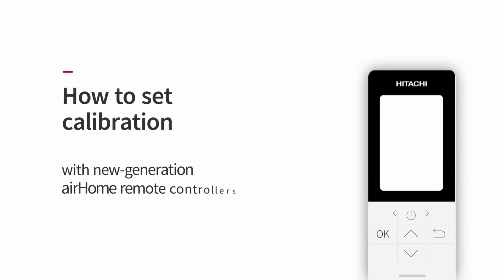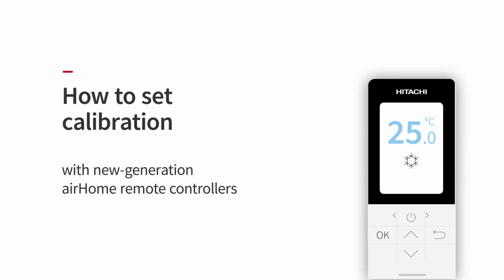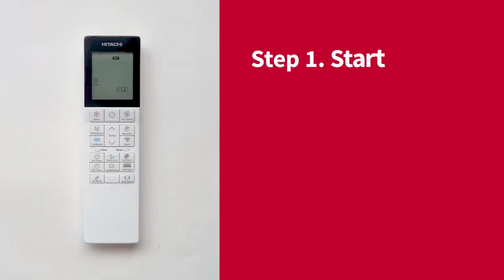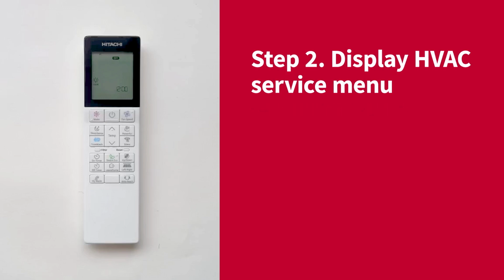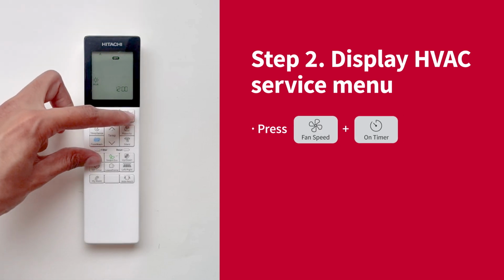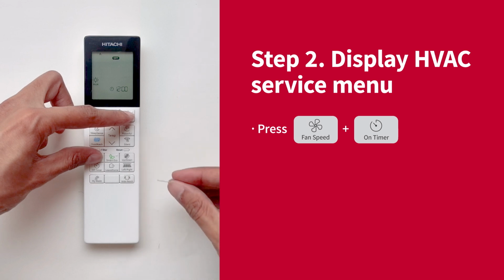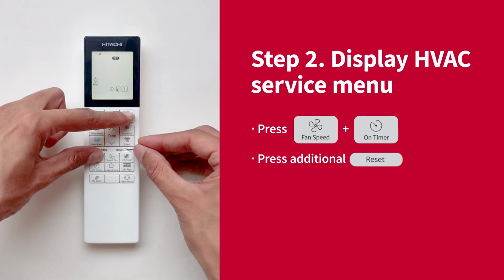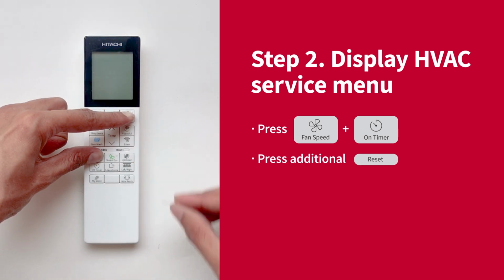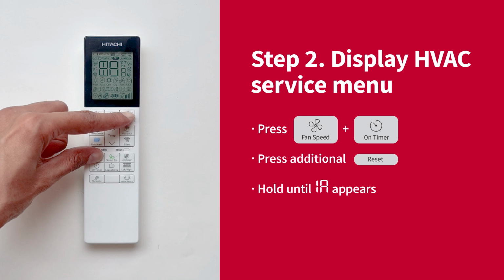Now let's see how to set calibration on the new generation airHome remote controls. Step 1. Pick up the remote control. It does not matter whether the air conditioner is on or off. Step 2. To make the HVAC servicing menu appear, press and hold the fan speed and on timer buttons simultaneously. While holding them down, briefly press the reset button. Keep pressing until the HVAC service menu appears, identified as 1A.